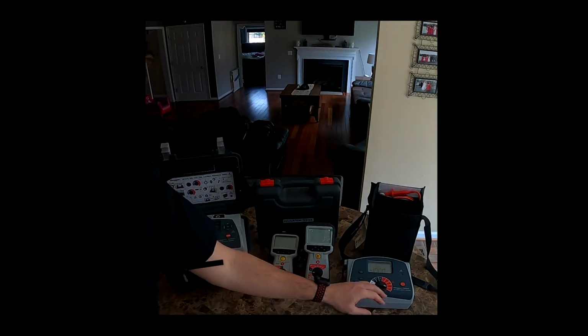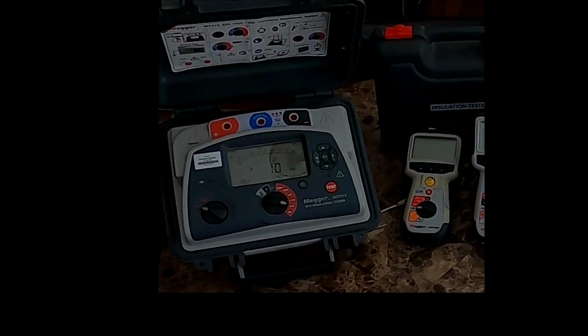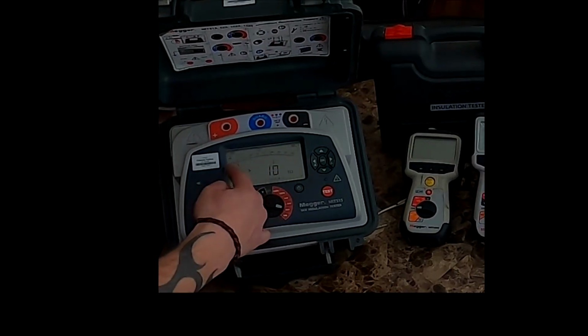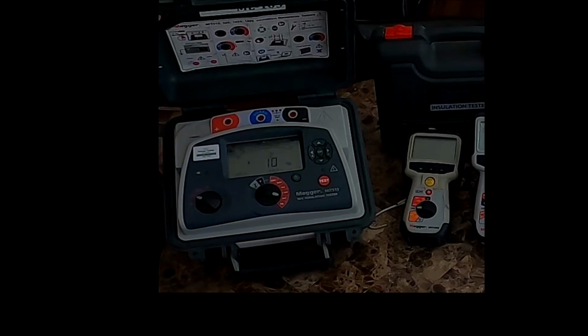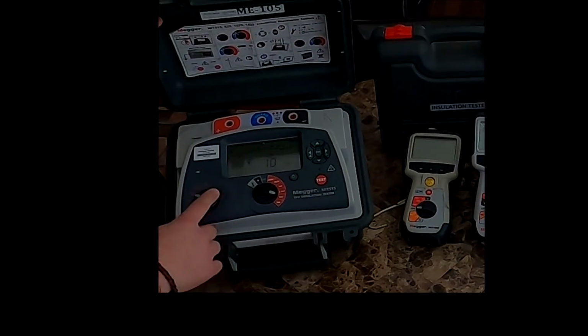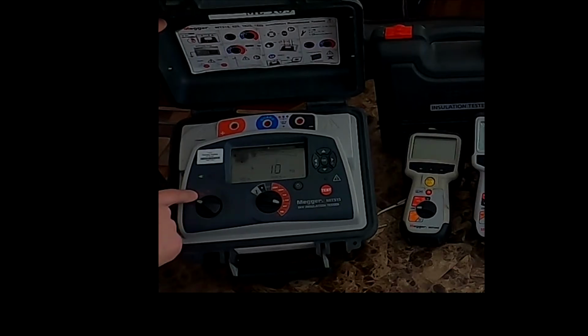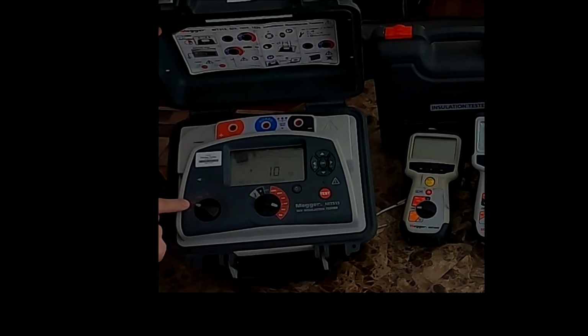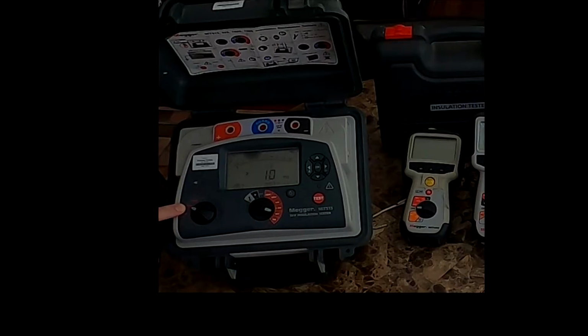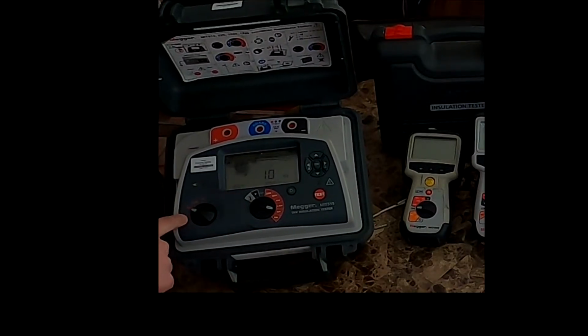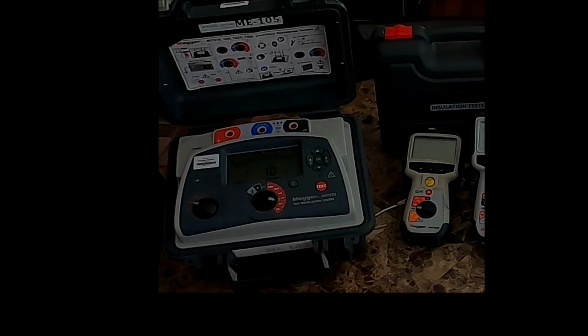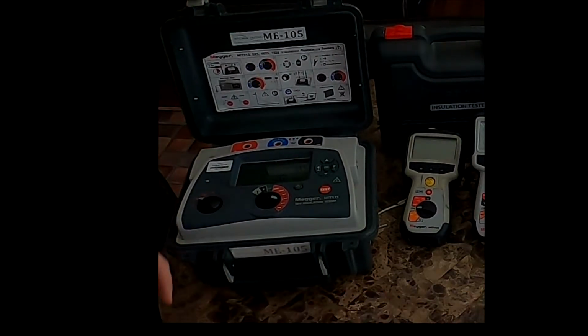I would like to use this more so on any type of larger equipment, transformers, but this does the job to check to see if there's any type of insulation fault at 5,000 volts. So they're both digital. They both show your voltage. They show an analog scale, and they have different modes. This one has the PI mode, a dielectric absorption rate, insulation resistance at a specific time, which can be programmed in the setup, and then just an insulation burn test that just stays on until you turn it off.